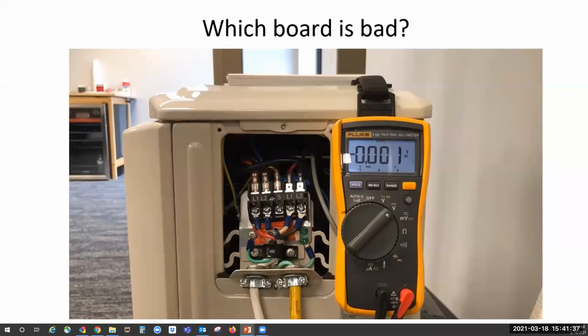Then you're going to switch it around. Your red lead stays on L2, but you move your black lead to the S wire that is coming from the indoor unit, and you're going to look for pulsating positive DC volts. Sometimes this does run pretty high. But if you don't see positive DC pulsating volts, then your indoor board is bad.